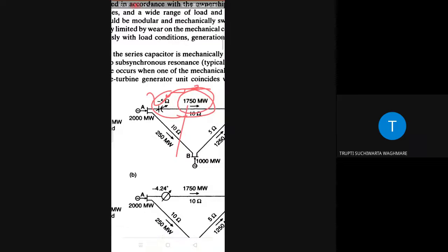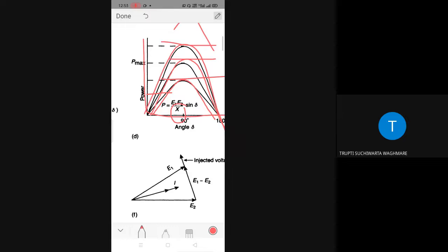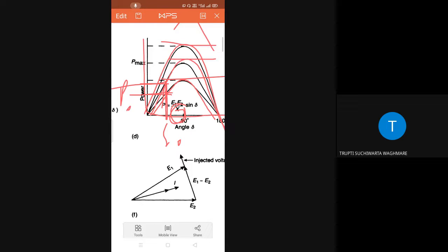So that is what is graphically explained here: how we modify the power angle curve of a given line by modifying its reactance, so that we can increase the power flow through a transmission line for the given condition. Given condition means, let's say this is the operating condition, so P flowing through the line and delta according to this line was this. Now I come to know that for this delta, the power flow P0 is 1400 megawatt, whereas the line has a capacity of 2000 megawatt. So I will reduce X. For the same delta, I can transfer this much power through the same transmission line. But this works when the loading is less than the thermal rating of the line: the thermal rating is much higher and the actual loading is lower, so to utilize it, we can do that. So this is how, by playing with X, we can do that.